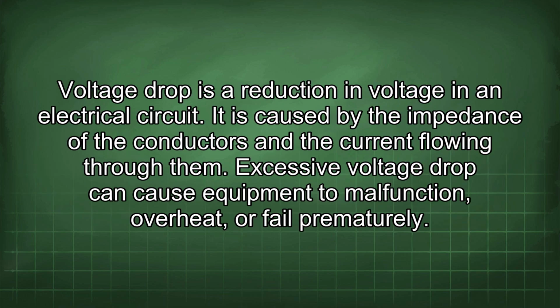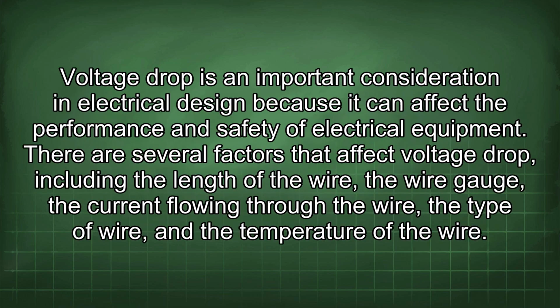Voltage drop is a reduction in voltage in an electrical circuit. It is caused by the impedance of the conductors and the current flowing through them. Excessive voltage drop can cause equipment to malfunction, overheat, or fail prematurely. Voltage drop is an important consideration in electrical design because it can affect the performance and safety of electrical equipment. There are several factors that affect voltage drop, including the length of the wire, the wire gauge, the current flowing through the wire, the type of wire, and the temperature of the wire.